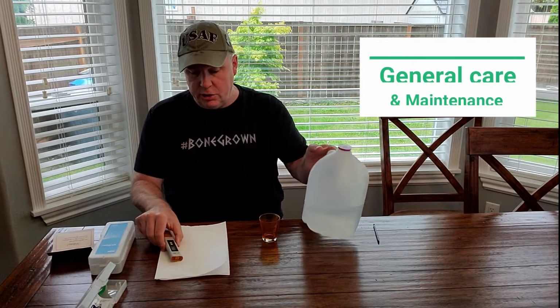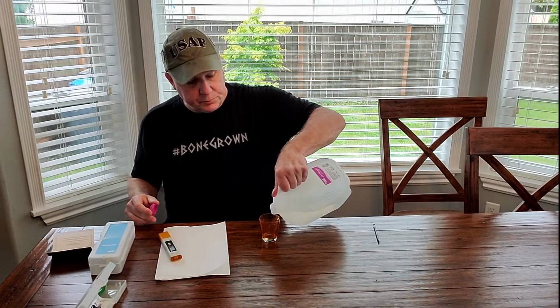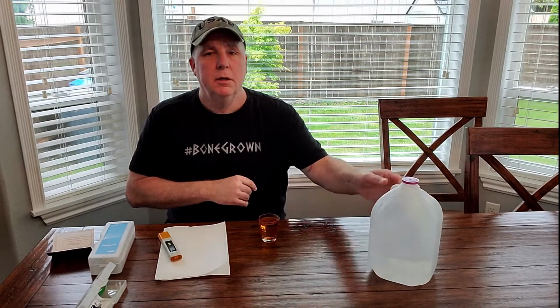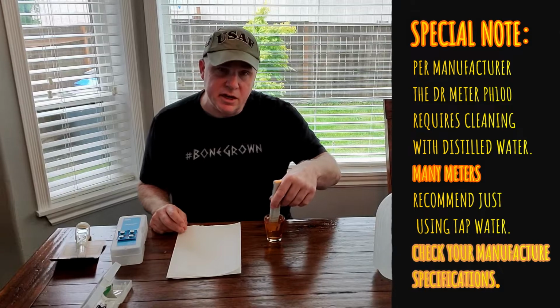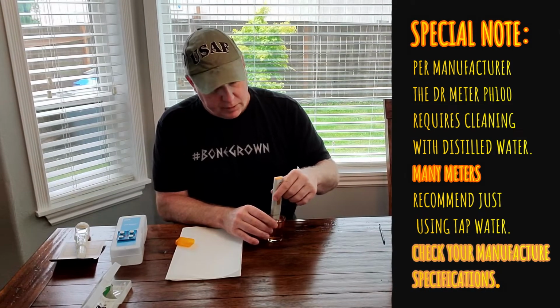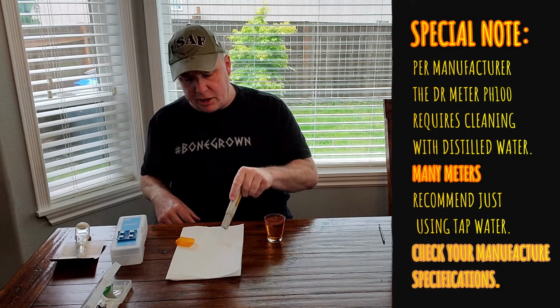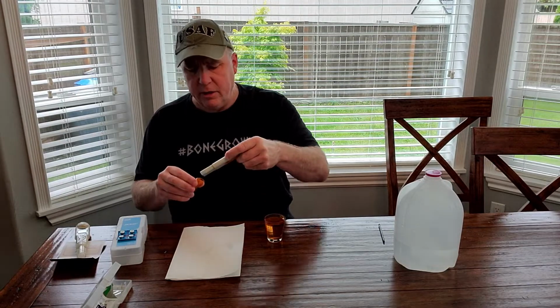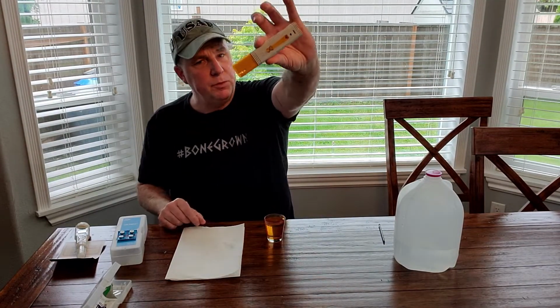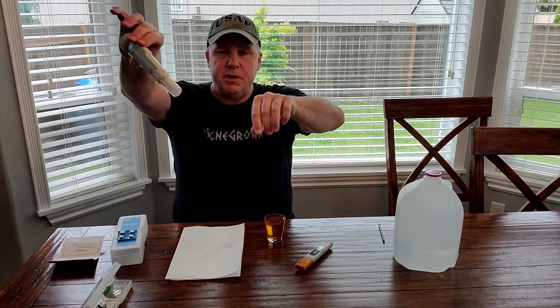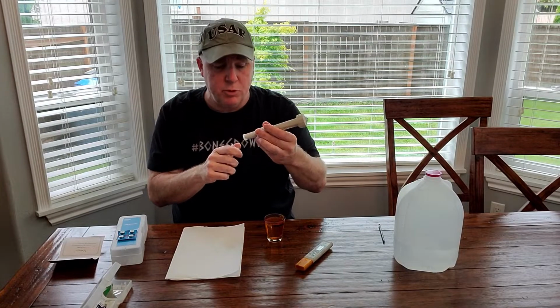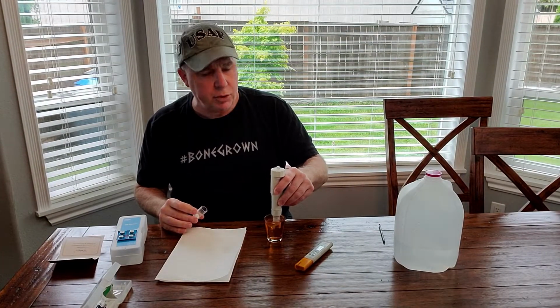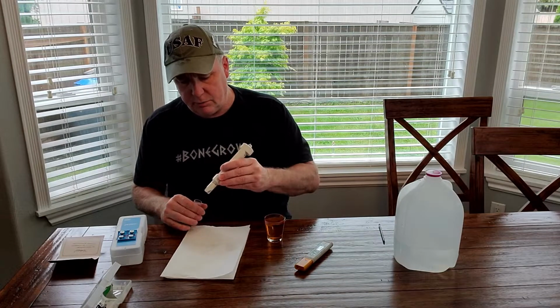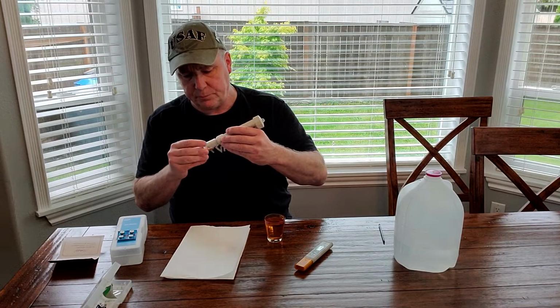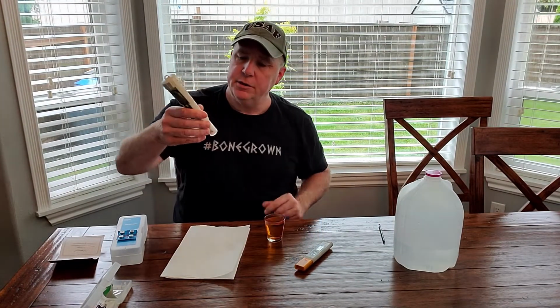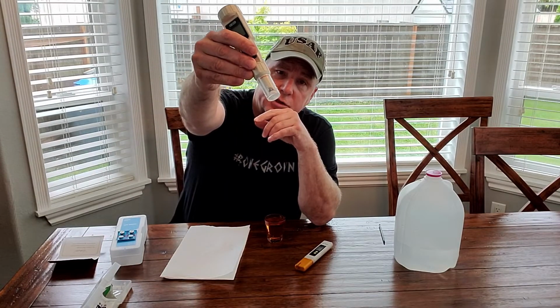Every time you get done with it, you should rinse off your pH meters. Whenever you get done doing a feeding of any kind, I prefer distilled water and cleaning off that electrode, and then when you get done, shake it off just like that. And then I shook it and I put it right back in the case. Do not throw these lids away. Same thing with this one. They normally will come with a little moisture in the end, and that's to ensure that there's moisture in there. I shake it just like I did the other one, and I put the lid back on. I do that because you do not want the diodes inside of here to dry out.